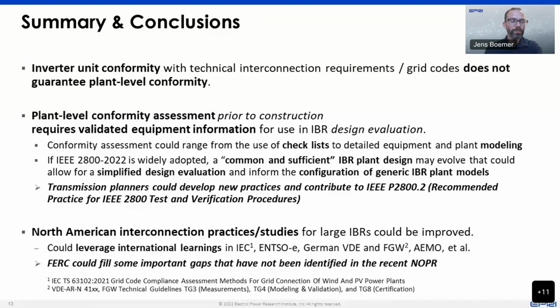In conclusion, inverter unit conformity does not guarantee plant level conformity. There's a step needed to translate one to the other. Plant level conformity assessment prior to construction really requires validated equipment information. That information could be modeling, but maybe a set of checklists could be sufficient to address most of the reliability issues we've seen to date, especially combined with adoption of IEEE 2800, which may lead to a common and sufficient plant design that simplifies design evaluation.